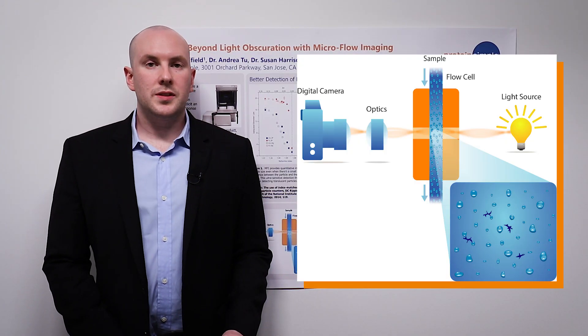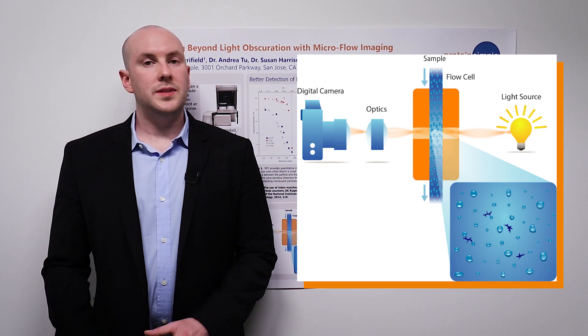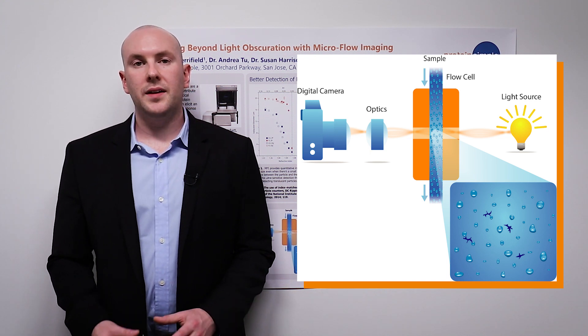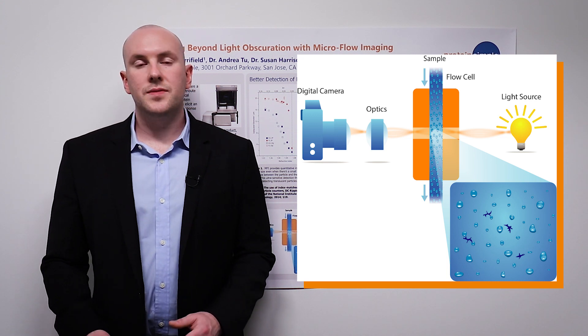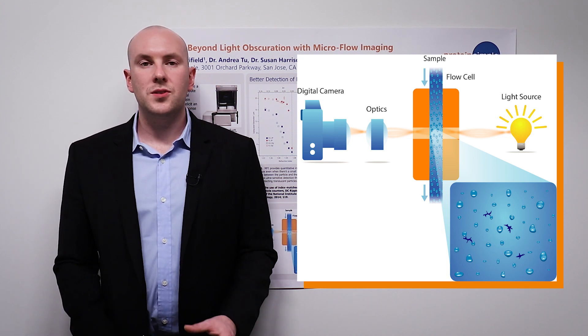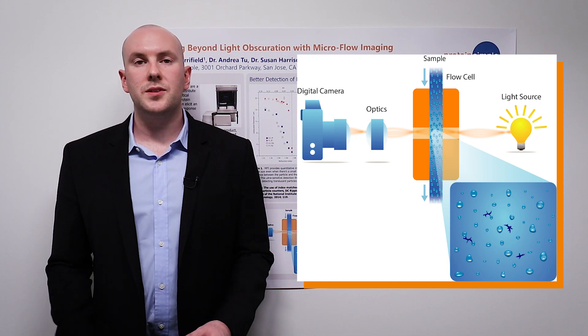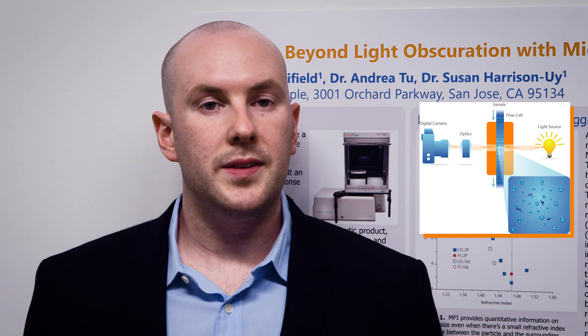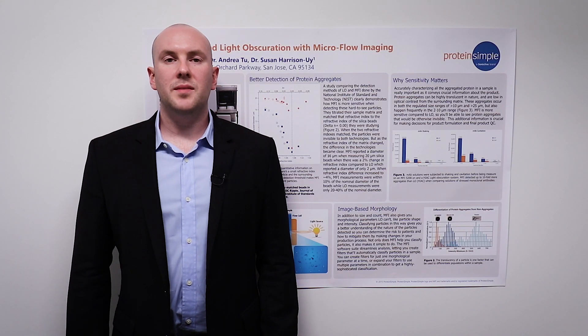The other thing that the flow cell ensures is that all the sample passes through the correct focal depth of the system. Any optical setup under magnification has a focal plane, and it's very important that all the particles are measured within the same focal plane to ensure that the measurements are accurate, precise, and that you can fairly compare particles measured in the same sample.